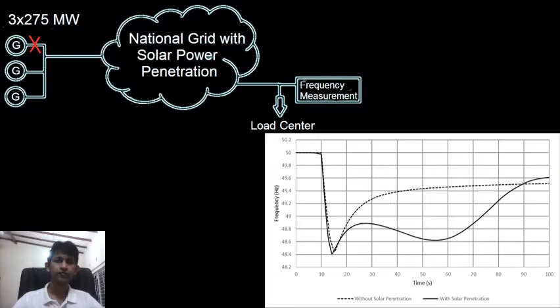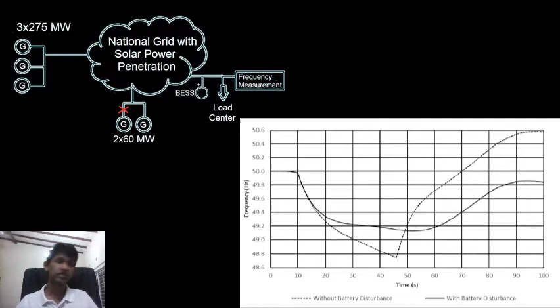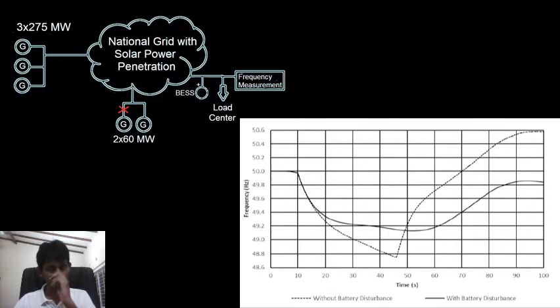Next, what we did was we did the same thing by tripping a 60 megawatt power plant. But this time we made a small change. We add a standby battery energy system storage so that as soon as the 60 megawatt generation goes out, this synchronized BESS gives power. It won't be giving power when there is no tripping. But as soon as the 60 megawatt generation is being reduced or taken out, this gives power and restores the frequency. As you can see in these two graphs, the dotted graph shows the frequency response without the battery energy system storage, and the solid line graph shows the frequency response when there is the battery energy system storage. So as you can see, there is no load shedding in the solid line.